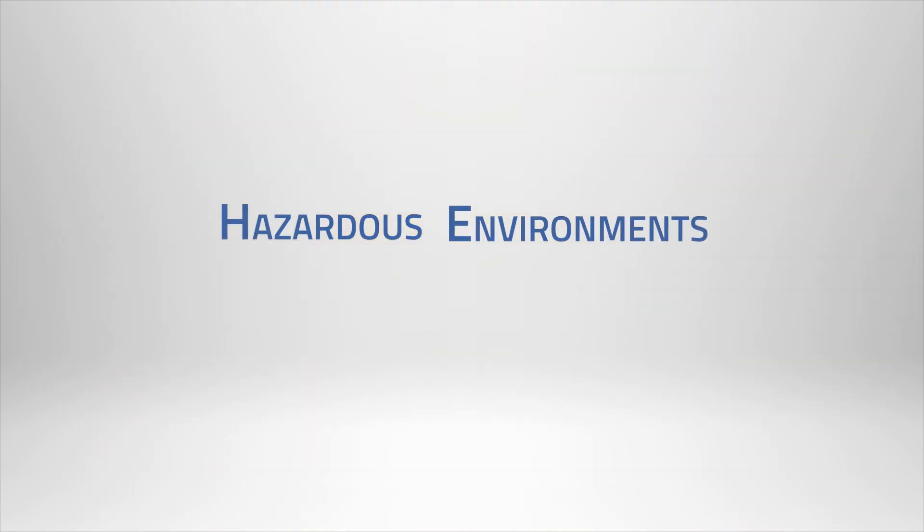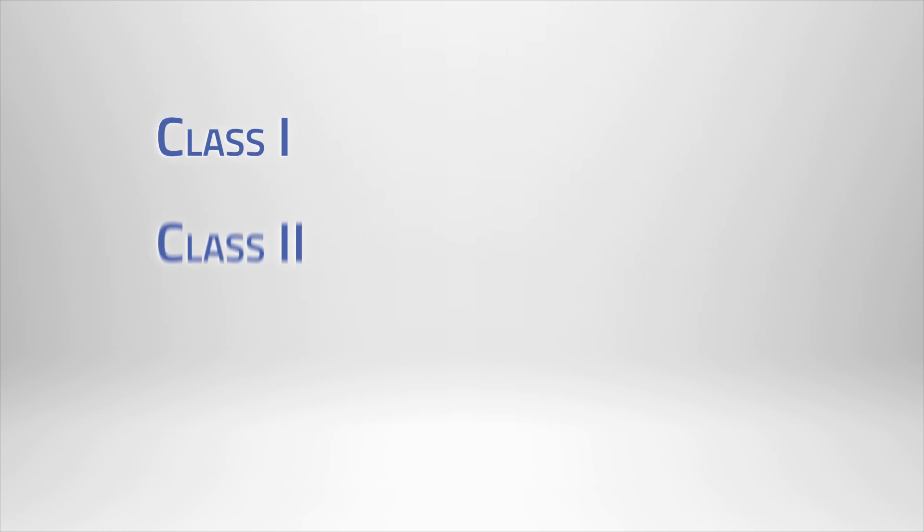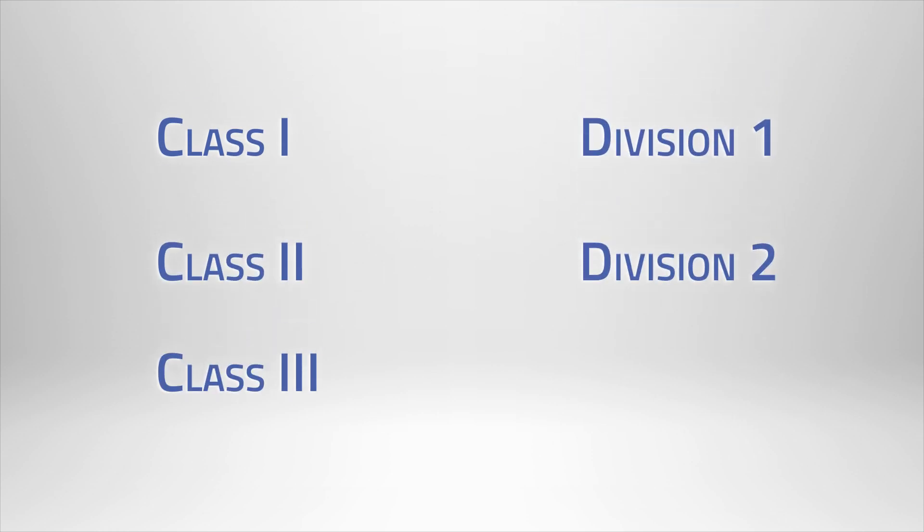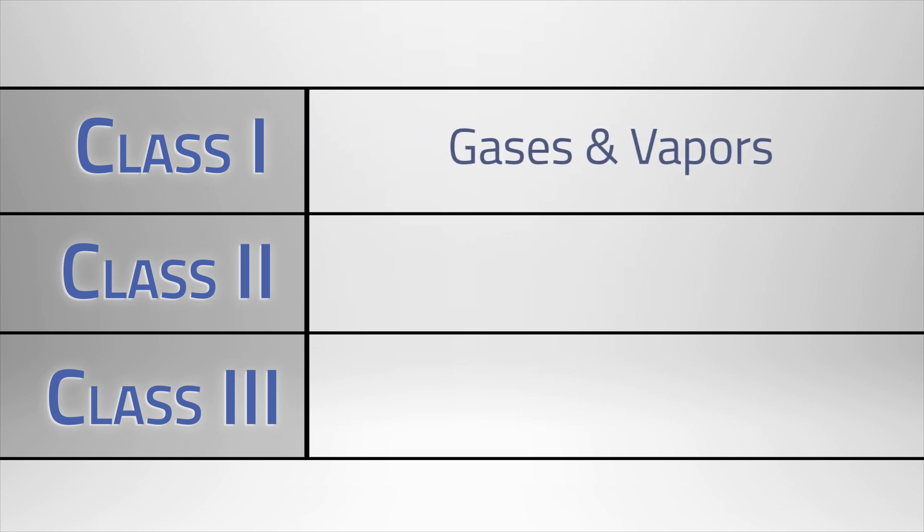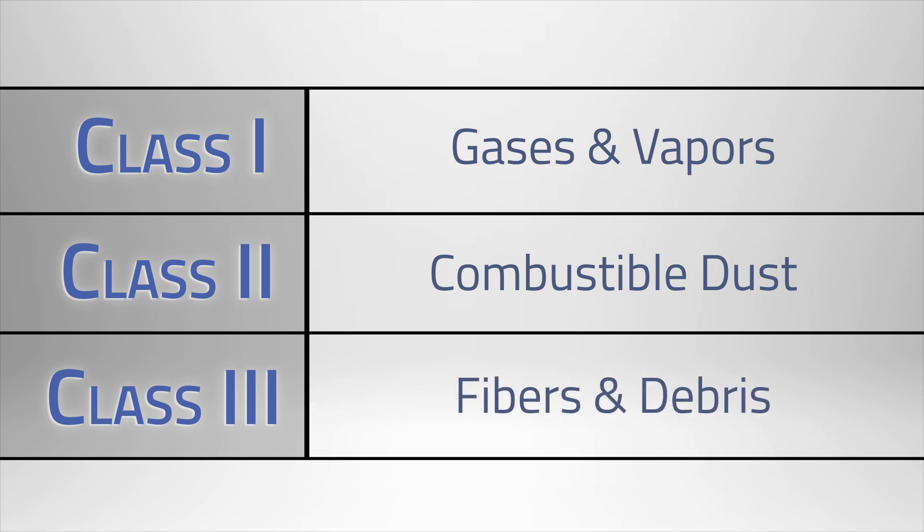Now what makes an environment hazardous? There are three classes and two divisions of hazardous environments. A Class 1 hazardous environment contains gases and vapors. A Class 2 environment contains combustible dust. And a Class 3 environment contains fibers and flying debris.